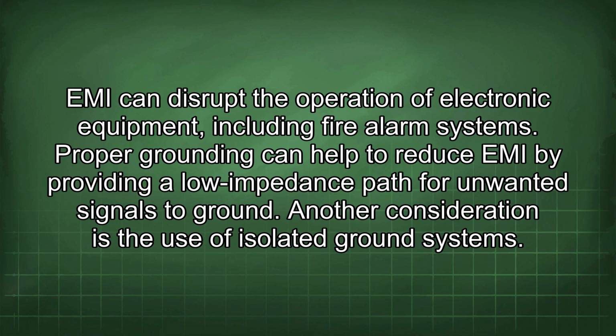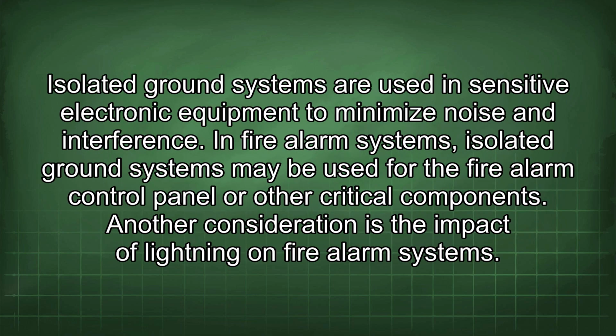Another consideration is the use of isolated ground systems. Isolated ground systems are used in sensitive electronic equipment to minimize noise and interference. In fire alarm systems, isolated ground systems may be used for the fire alarm control panel or other critical components.